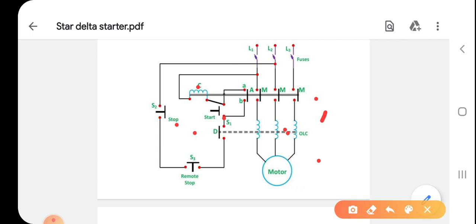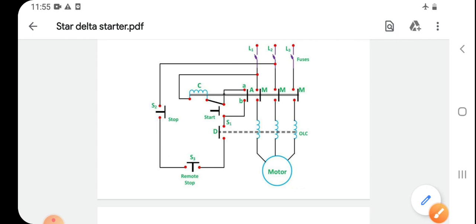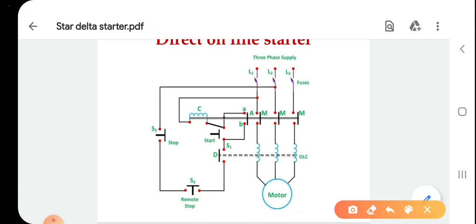The start button may be installed in a convenient place from the starter. The start button is held open by a spring. On pressing the start push button S1, the contactor C is energized from the two lines L1 and L2. The three main contacts M and auxiliary contact A are closed, terminals A and B are short-circuited, and the motor is then connected to the supply mains.